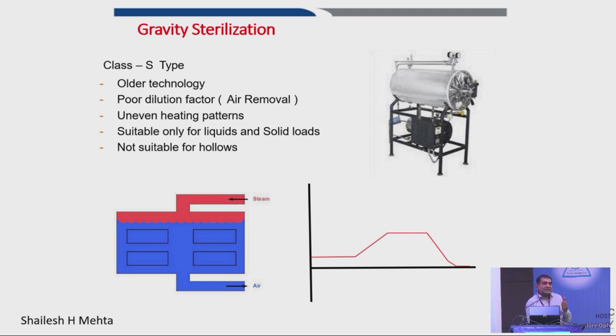So there's something called a sterility assurance level for OT. There's something called a sterility assurance for CSSD. So in this particular kind of process, whether S or N, you never achieve it. In case you have any implants, whether orthopedic or ophthalmic, you can't put them into this process. The cross-infection rates to the patient are so high. So you have to understand the limitation of each process.